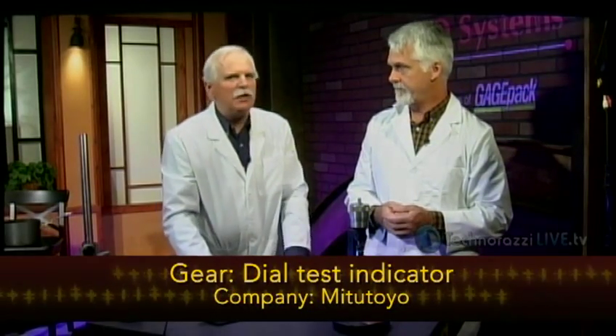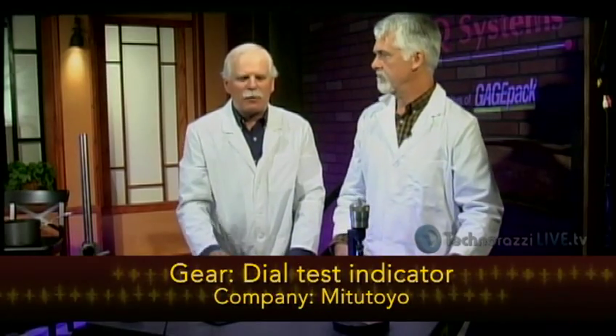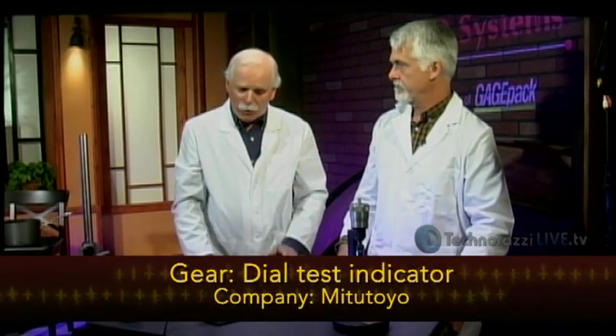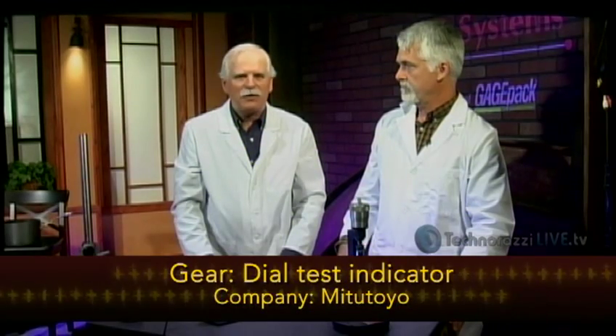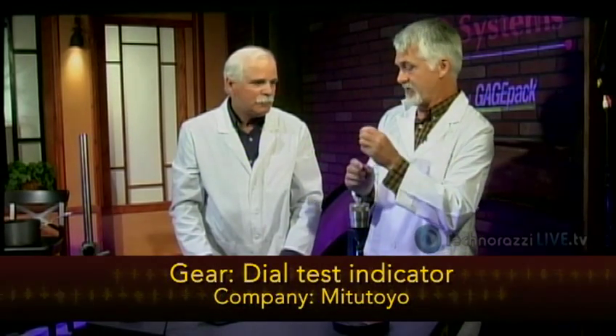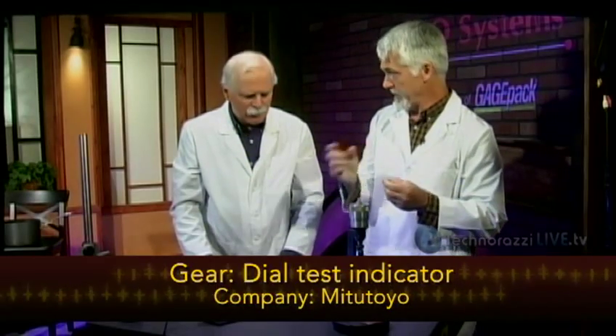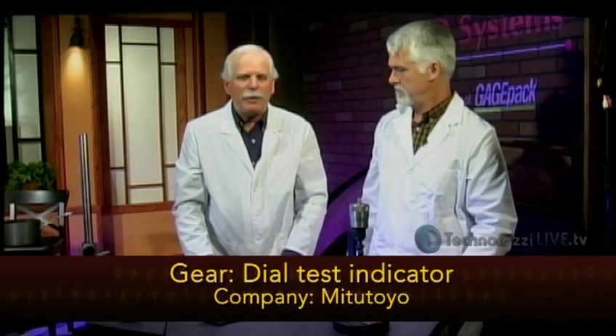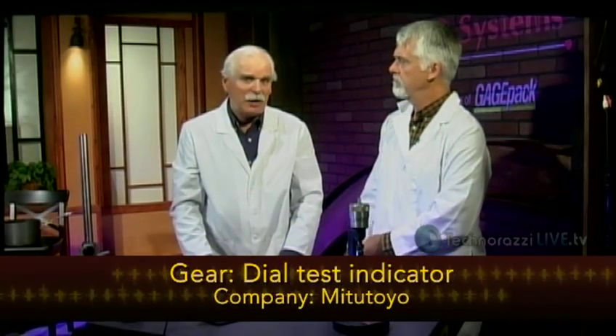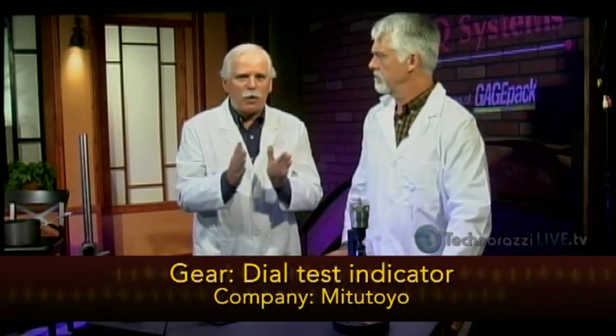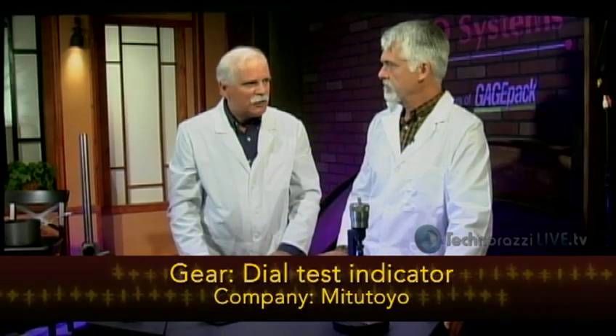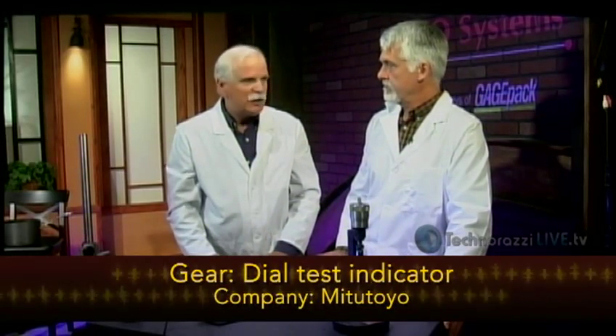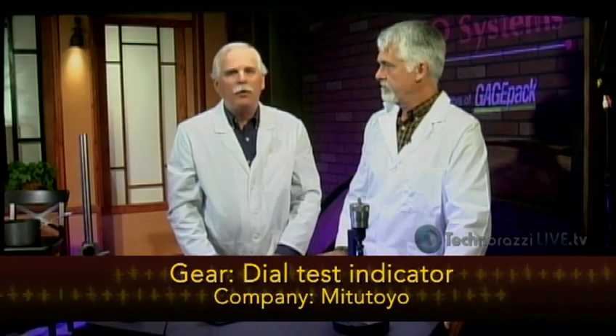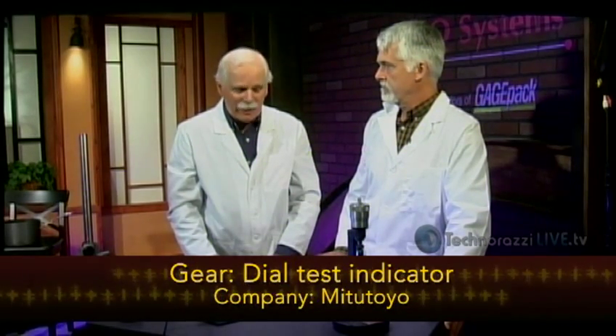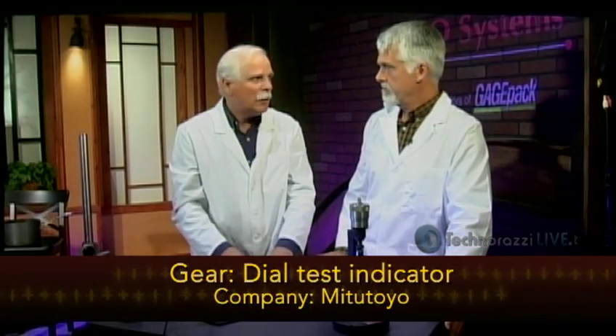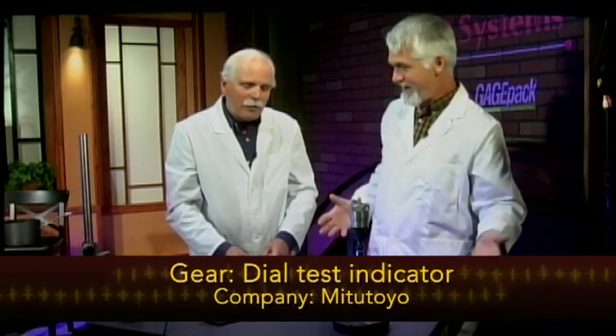And that's true. And what happens in that case is when we calibrate them, the tolerance is plus or minus 1 division. With the wrong length tip, even 3, 4, 5 thousandths difference. And by wrong length, we mean it's a cheap tip, so it's not precisely the right length. It's inexpensive. They didn't spend a lot of time measuring them. They might have used cheaper material, but it's the wrong length, just a little bit, 4 or 5 thousandths of an inch. It will be off 2 or 3 divisions, and we can't get it to come in. We'll pull that tip off and say you need to get the correct length, even though they'll swear up and down they just bought a new one. It was 3 for $1. Come on. They got 2 left.